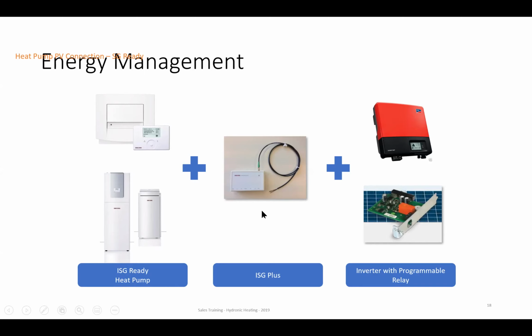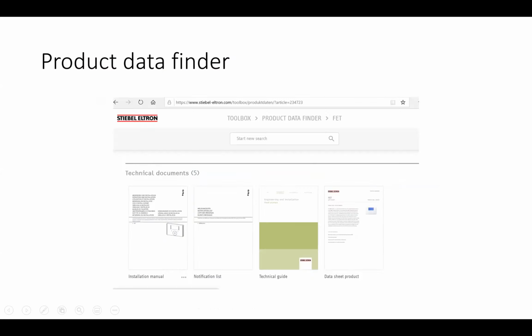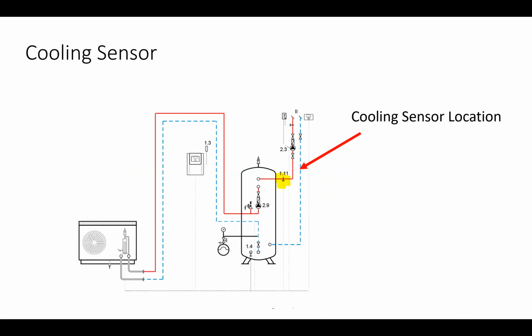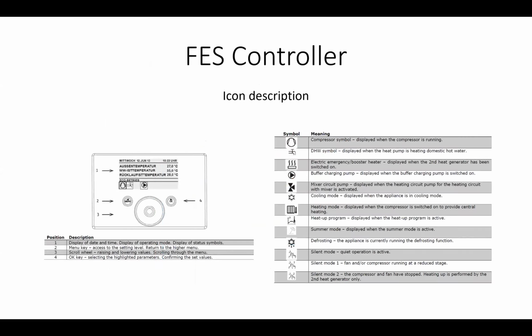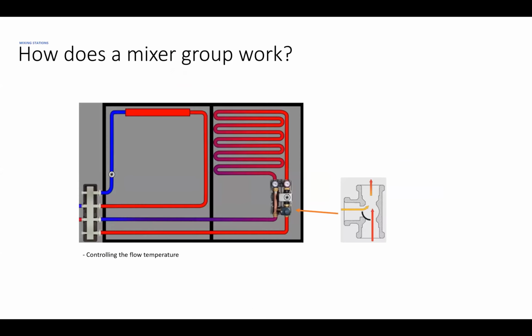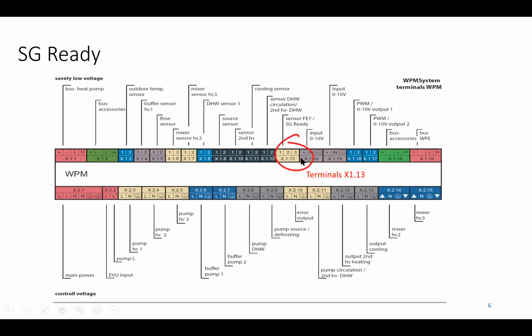Now what that does—sorry, I'll just find the slide, it's in the wrong spot—we send a signal to, once again, X113, and we will close those contacts. Now X113 can't be used for more than one function, and you'll note we were talking about it with third-party control. So unfortunately we can't use that for solar energy management mode and a third-party stat at the same time. We can only choose one function. So be aware—we should pick up on that though when we're helping with design.